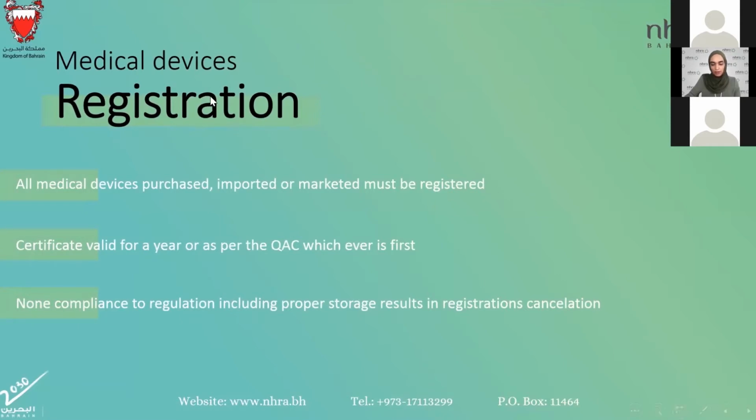What is it highlighting? It is actually putting a legal framework of what we have been doing since 2016. All medical devices purchased, imported, or marketed must be registered. Certificate is valid for 1 year, or as per the QAC, whichever is first.